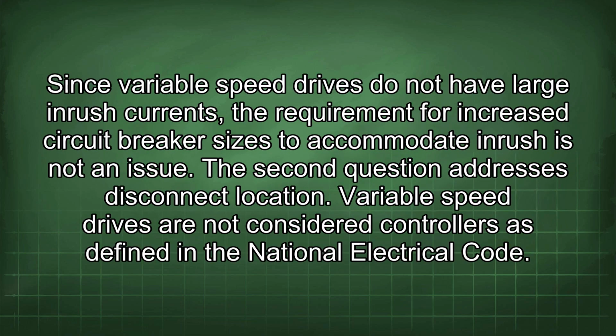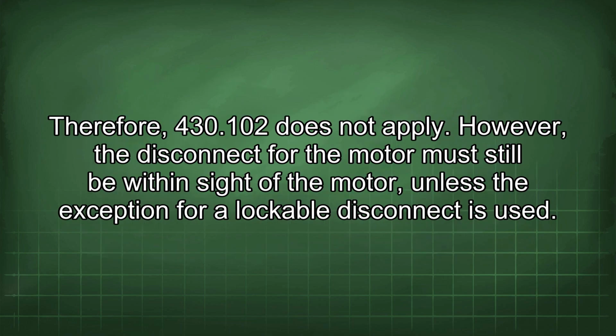Since variable speed drives do not have large inrush currents, the requirement for increased circuit breaker sizes to accommodate inrush is not an issue. The second question addresses disconnect location. Variable speed drives are not considered controllers as defined in the National Electrical Code. Therefore, 430.102 does not apply. However, the disconnect for the motor must still be within sight of the motor, unless the exception for a lockable disconnect is used.